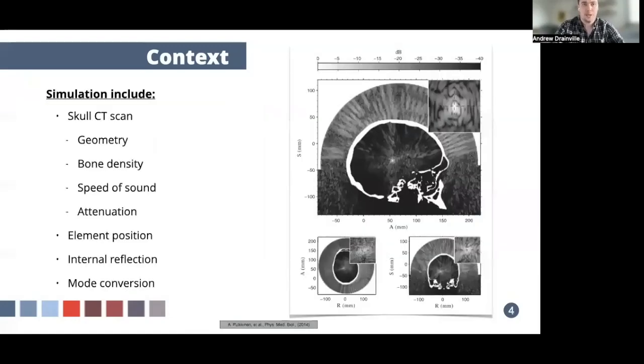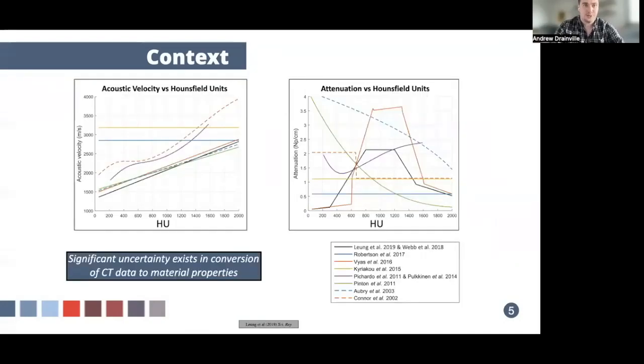Skull material properties are most commonly estimated using CT scans, which provide both detailed information on the shape of the skull as well as measurements of bone density, which can then be used to estimate acoustic properties of the skull, including the speed of sound and the attenuation. A problem, which is illustrated in the figure on the left, is that there are many different published conversion algorithms to estimate the speed of sound, and they don't all agree with each other. There's even less agreement on how best to derive attenuation properties from CT data, and it's important to know how uncertainty in these properties can affect transcranial focusing.